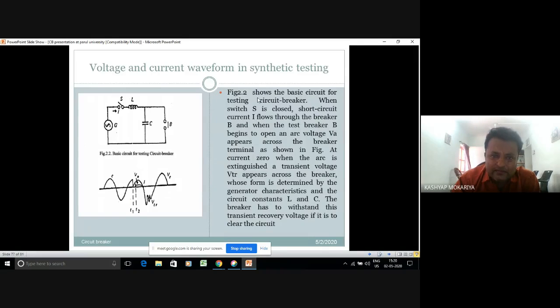You can see here the basic circuit for testing a circuit breaker. When switch S is closed, short circuit current I flows to the breaker B, and when the test breaker B begins to open, an arc voltage, shown here, appears across the breaker terminal. At current zero, when the arc is extinguished, a TRV, a transient recovery voltage, is produced across the breaker, whose form is determined by the generator characteristic and the circuit constants L and C. The breaker has to withstand the transient voltage if it is to clear the circuit.